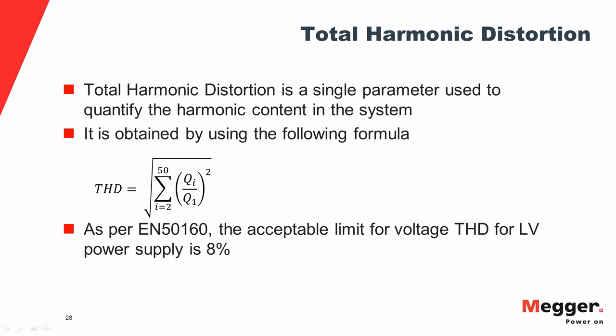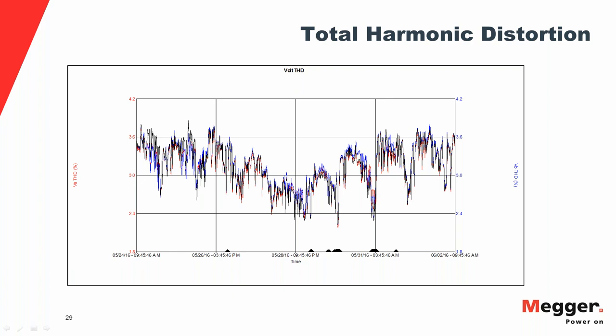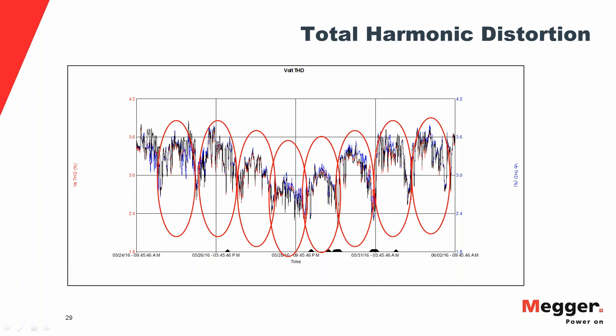Looking at a THD chart from a week-long recording — about eight days — you can see a repeating pattern, with each cycle corresponding to one day. This is because THD corresponds to the load of the plant. That's why it's essential when doing harmonic measurements at a facility to keep the recorder in place for at least a week to get the full picture.